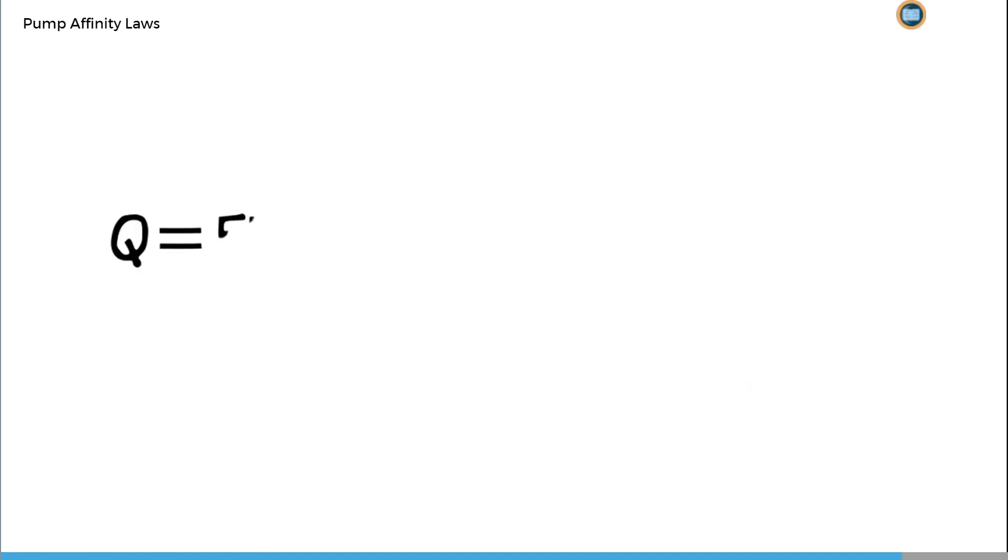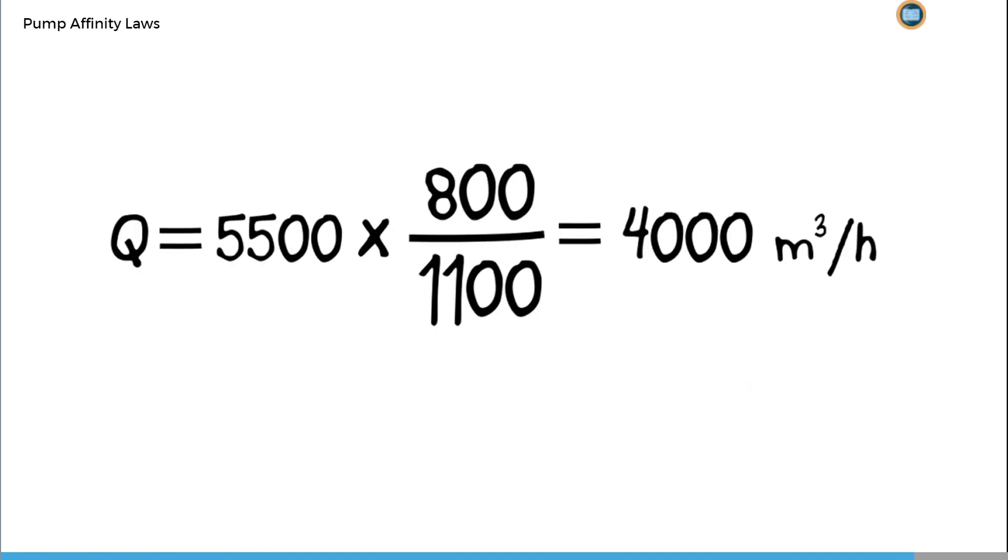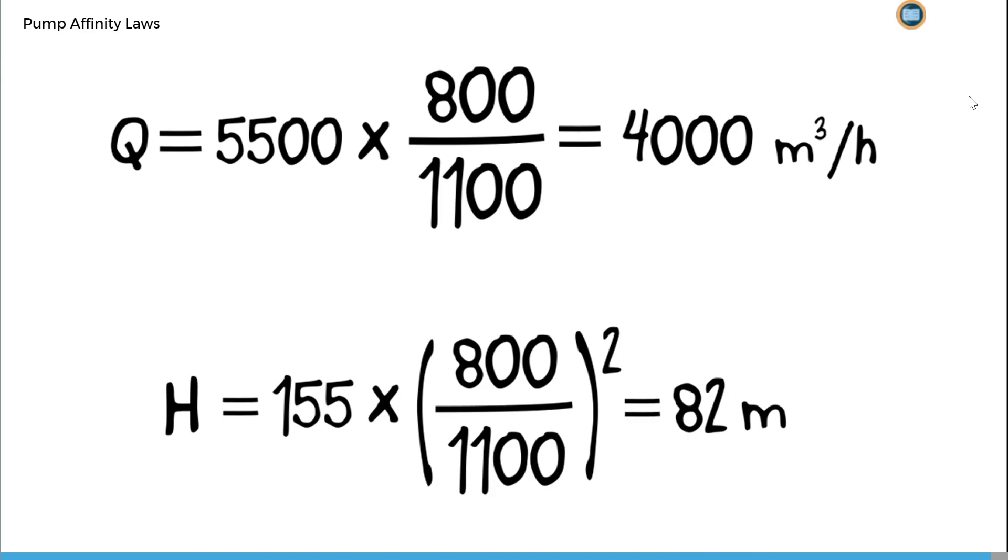If we now calculate the flow rate using these expressions for a rotational speed of 800 revolutions per minute, this gives us a flow rate, Q, of 4000 m³ per hour, and a head, H, of 82 m.